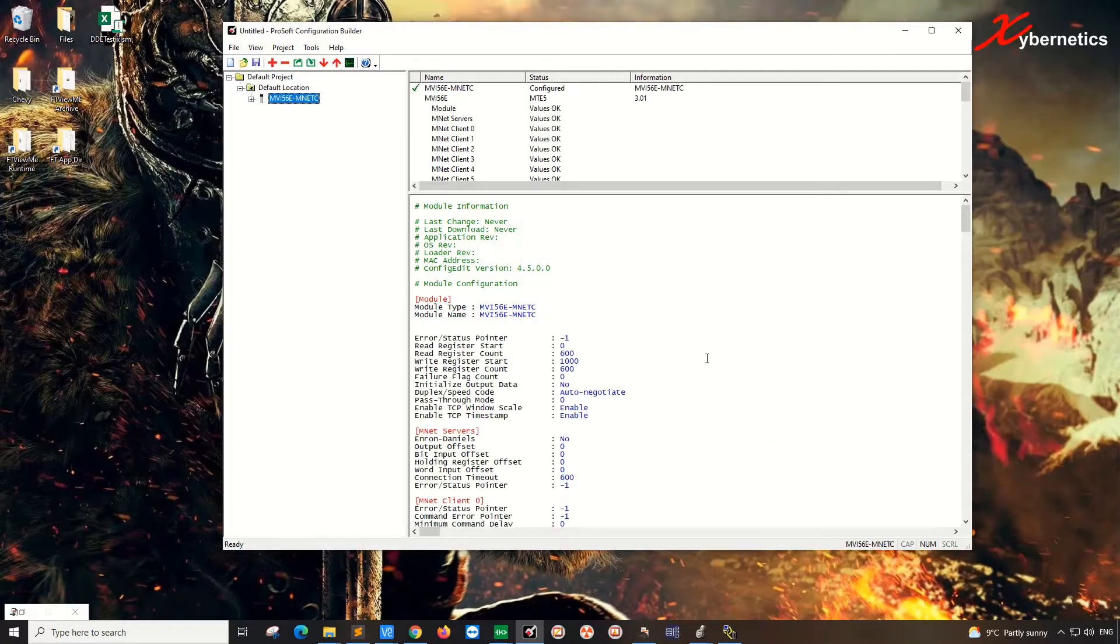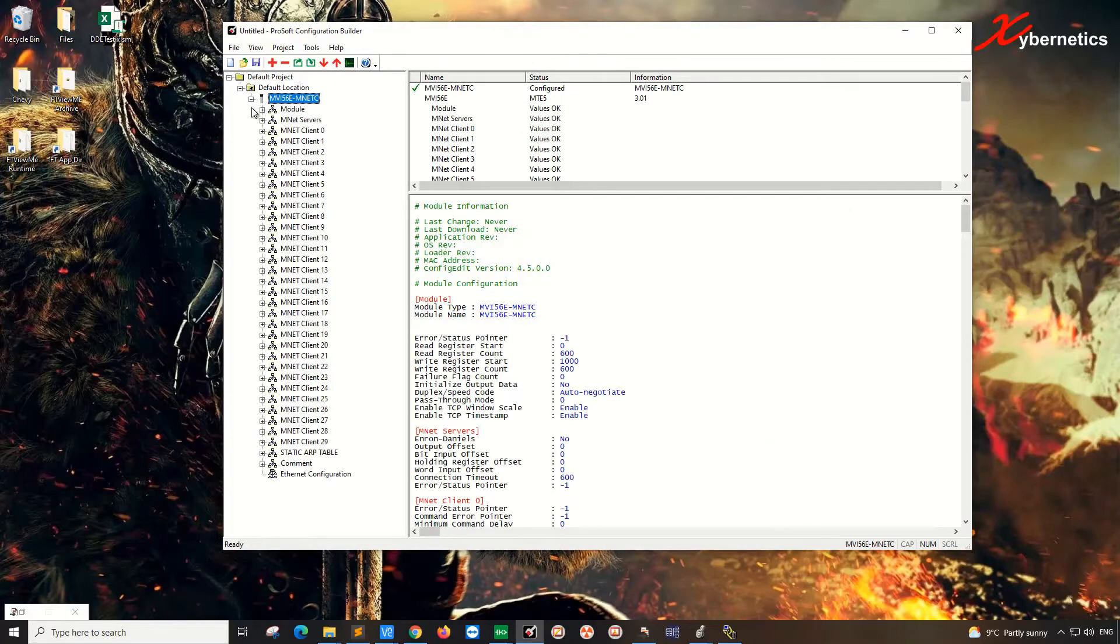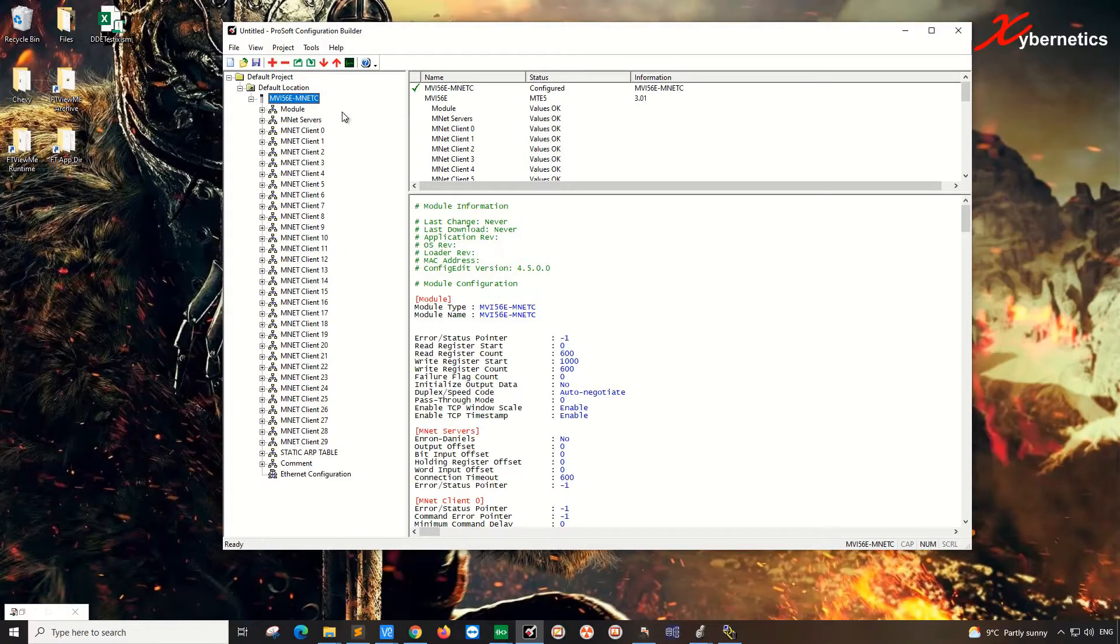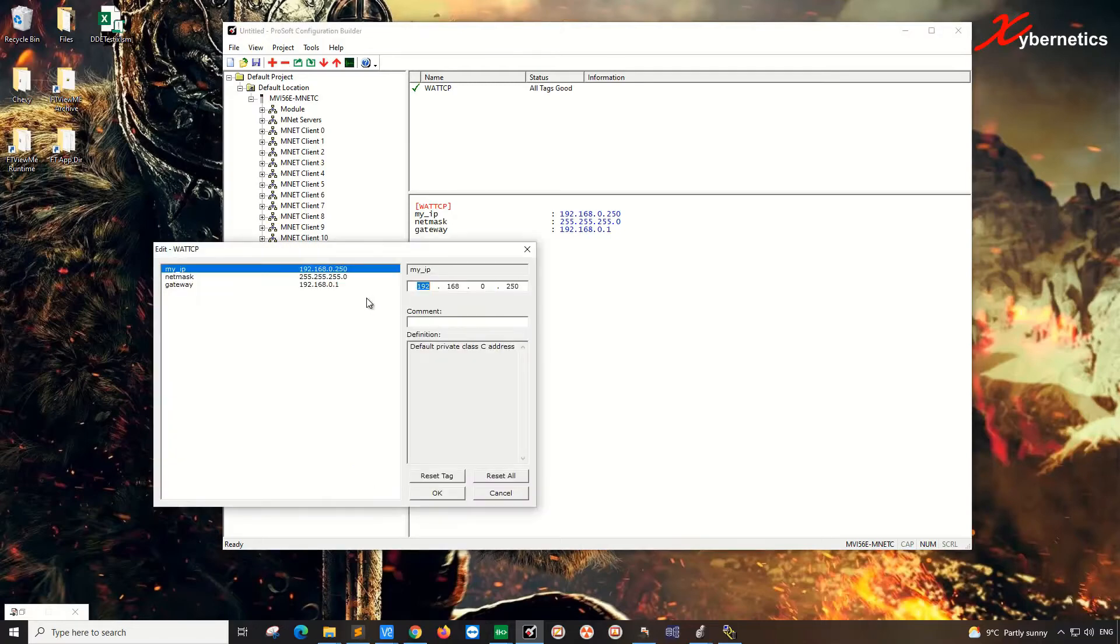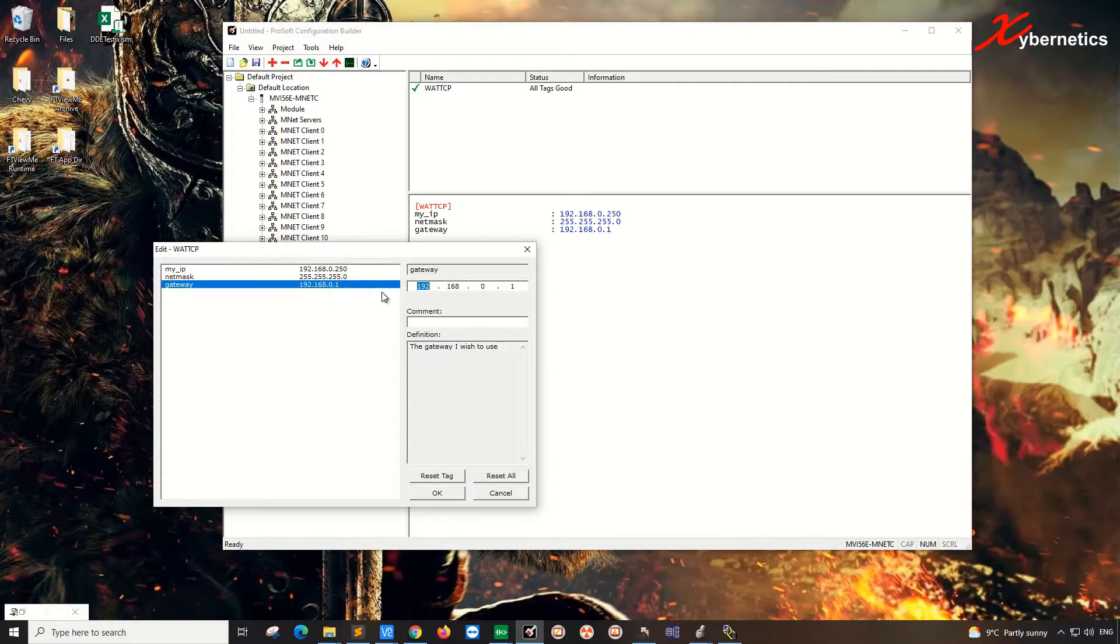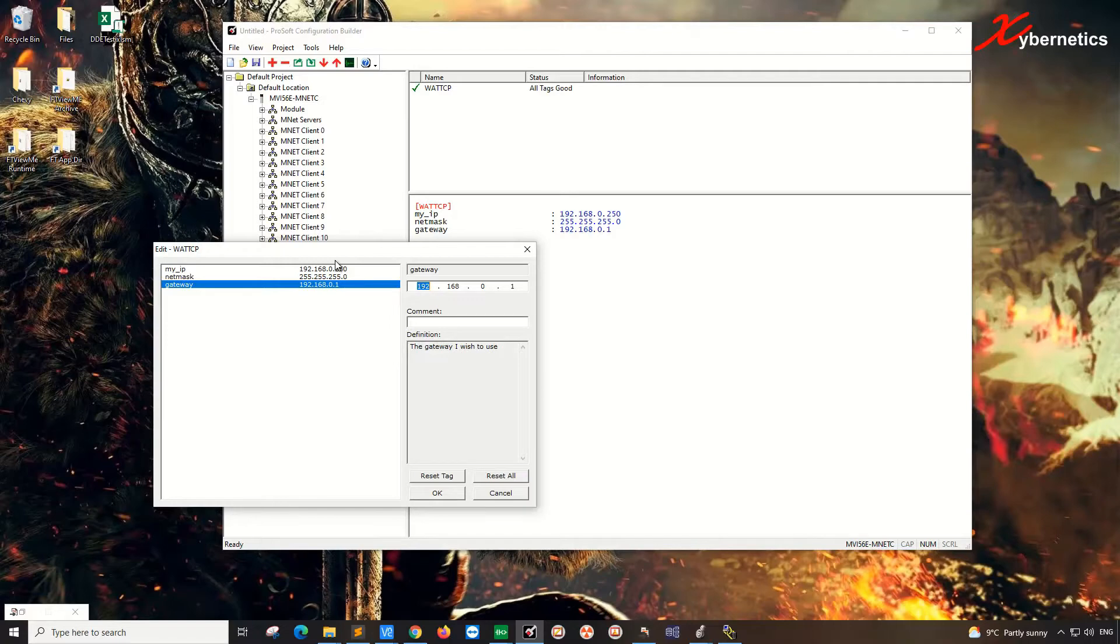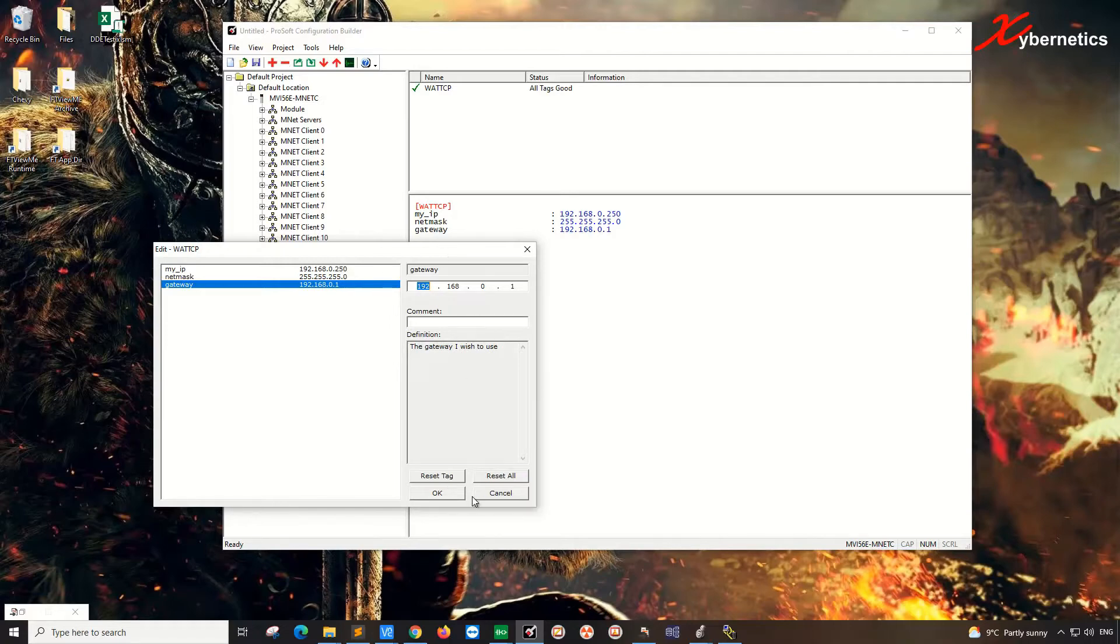Once you click OK, the tree on the left hand side of the ProSoft Builder will be built according to what the module is able to handle or designed for. And over here, of course, you're going to have to set the Ethernet configuration. So you double click it and enter the IP address, subnet mask, and the gateway. So enter all those appropriate details in there. And this is the IP address of the Ethernet port that's located at the front of the MNET or the MVI-56E MNET-C card. So once you've set this up, click OK.